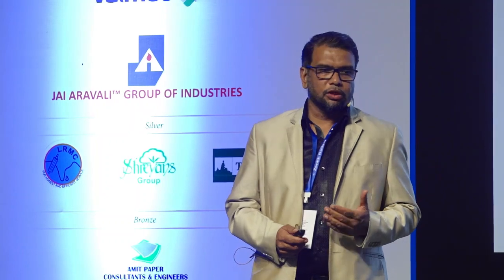In the process of preparing for green manufacturing in the paper industries, I wanted to present two projects which we have already done successfully. It is working. The concept was that in our pulp effluent, the effluent temperature is about 70 to 75 degrees, due to which the biological treatment of the ETP is severely affected. The waste heat from pulp mill effluent can be recovered and used as boiler makeup water and to cater to the hot water requirement of the paper mill to reduce the process steam requirement.